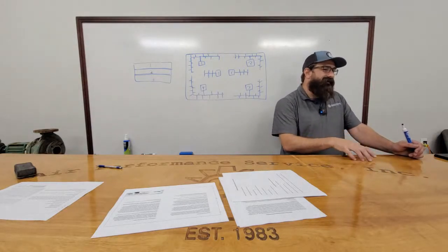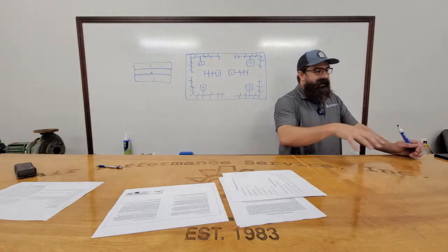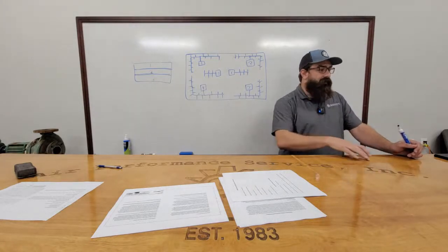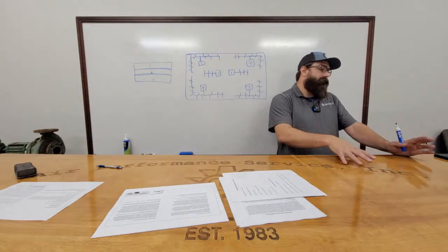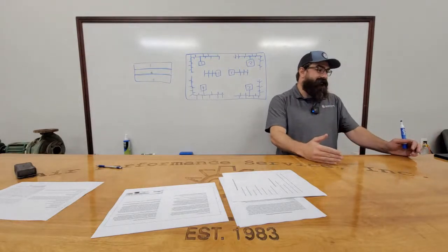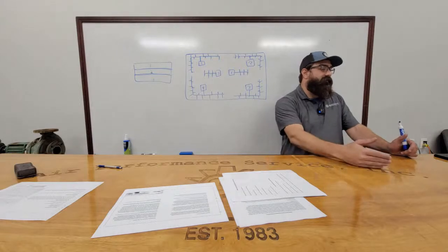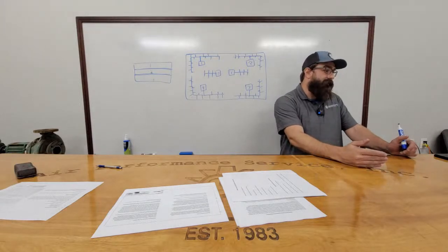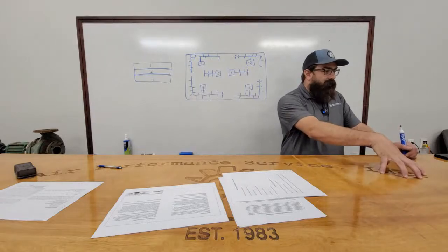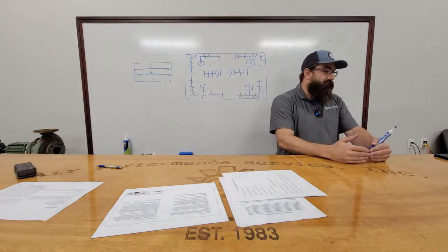So I think we may do like 5 or 6 units at a time. We let them come on per floor, however long it takes to bring all the equipment on to enable. It may not all start up at once because it's still maintaining a set point, right? So out of 5, you may only have 3 that engage at any one time. But if you bring on the entire floor, that's still a ton of equipment that could possibly come on at any one time.